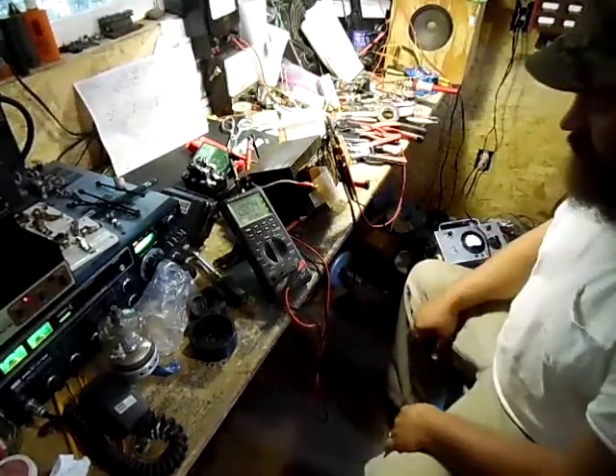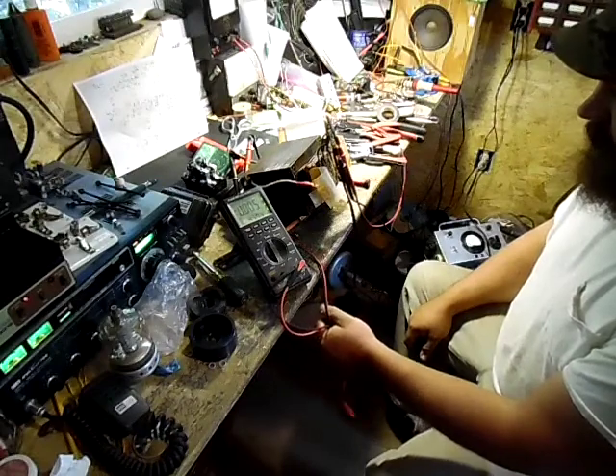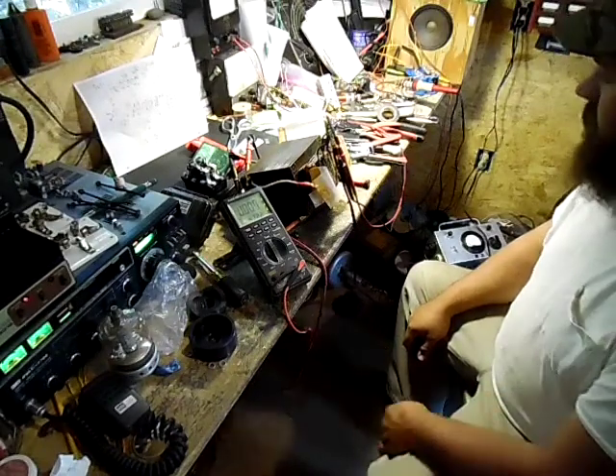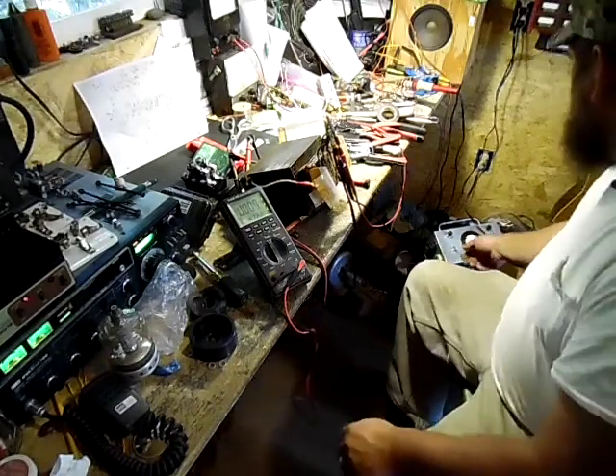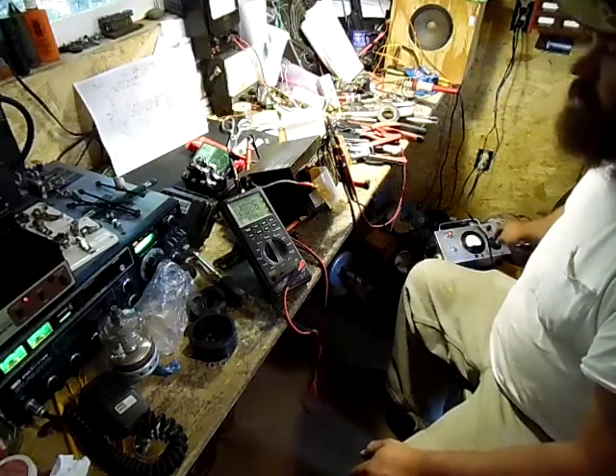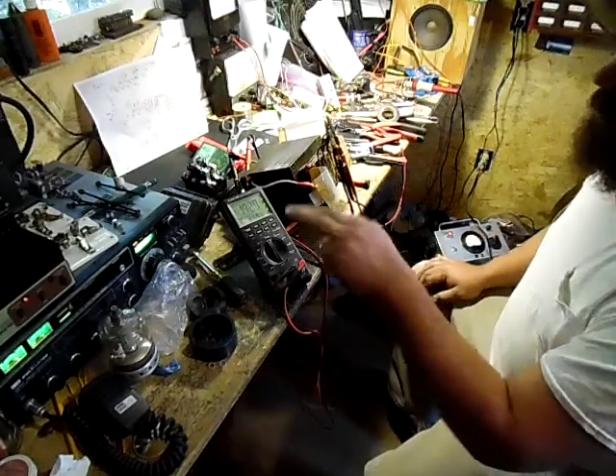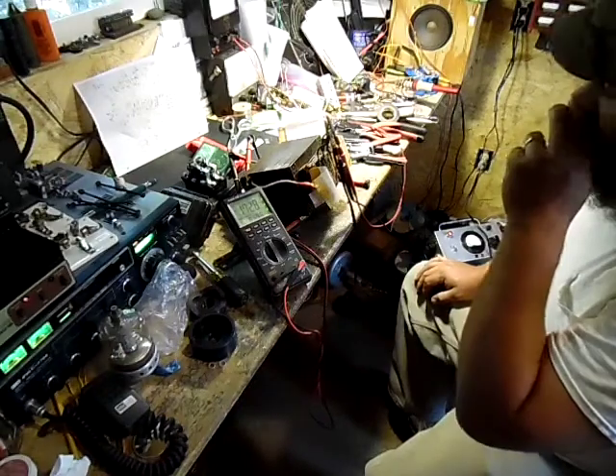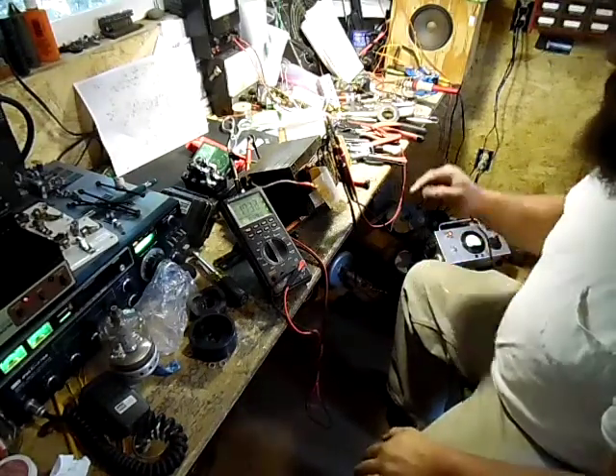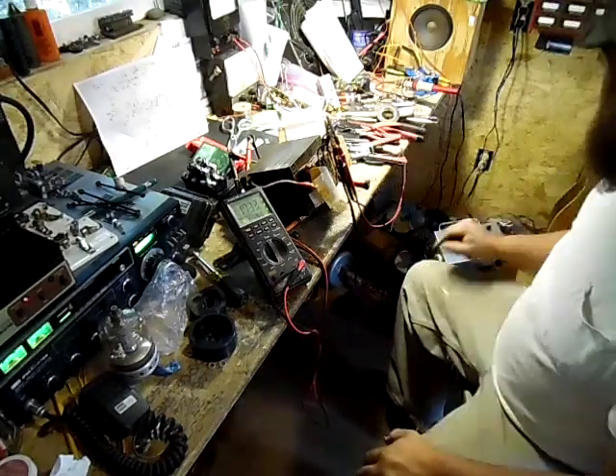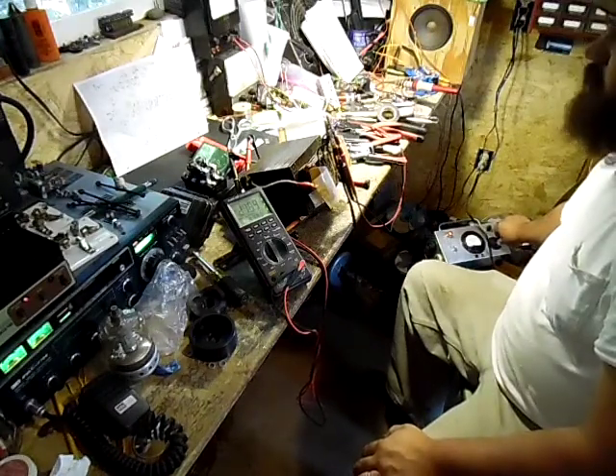And the Simpson meter, I always sit back from these because this lead's going to be handling 800 volts. And so if it had a cut in it, you're going to get it. So, all right, my variac's on, and you see with the variac all the way down, it's showing 1.5 volts on the high voltage side. And with the variac all the way down, this side's not showing anything. So let's start cranking it up.